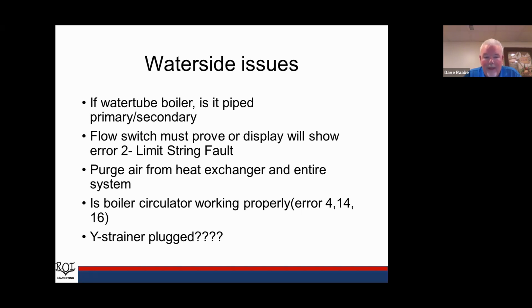So, is the boiler circulator working properly? We might get an error number 4, 14, or 16. This could be too high of a temperature rise or too high of a temperature, period. You know what happens in these water tube boilers, they may only have a quart or 2 quarts of water in the heat exchanger, and we might be firing them at 180, 199,000 BTUs. So flow becomes very critical. If the proper flow is not there, we can actually flash the steam in that heat exchanger. We're going to see too high of a temperature rise, and that will give us an error as well.